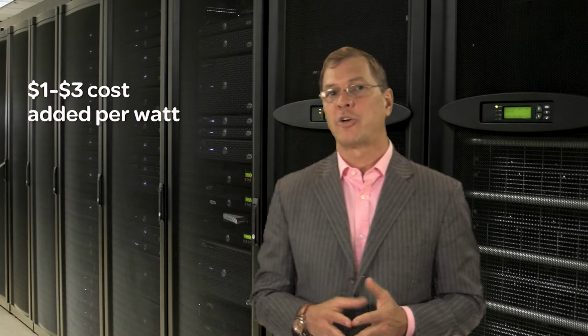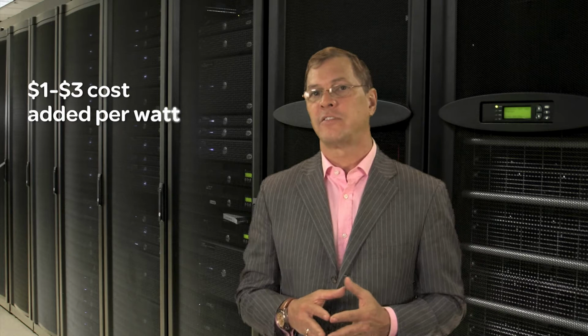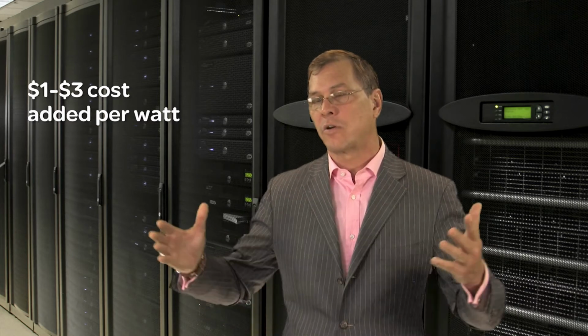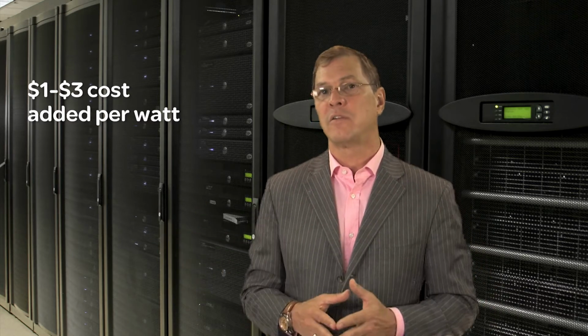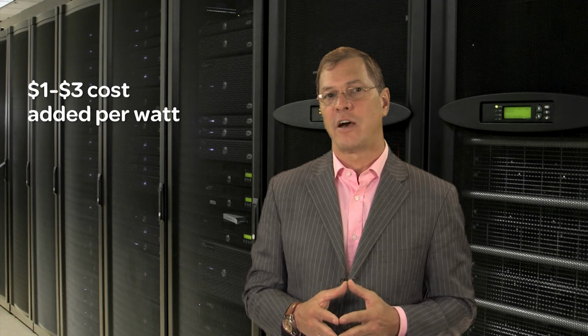And one of the things this drives is the need to put in dual path UPSs, static switches, cross connects, and many devices in our data center infrastructure systems that contribute to the complexity of those systems and also to their cost. In fact, they can add $1 to $3 per watt to the cost of a data center, which could be on the order of 10 to 20, 30% of the entire cost of the physical infrastructure of the data center.